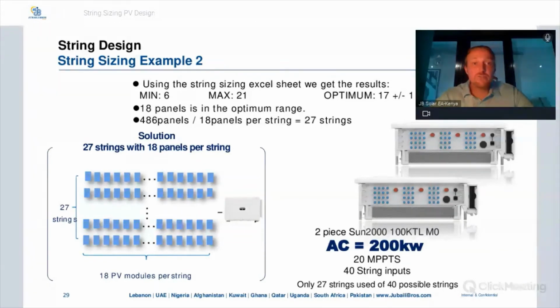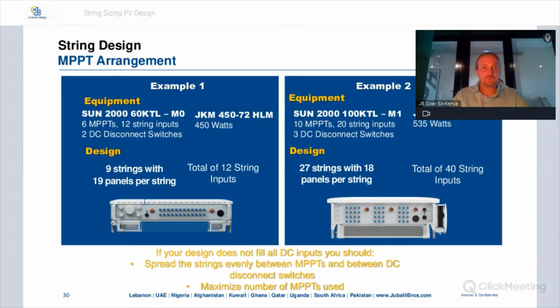Now, we're only using 27 in total, and we have 40 available because there are 20 on each inverter. So we have 27 strings, but we have 40 inputs available. Again, many string inputs will be empty, and that's okay. If we follow the steps and do our calculations, this will be fine. But look at what we have. In example 1, we're using 9 strings out of 12. And in example 2, we're using 27 strings out of 40.